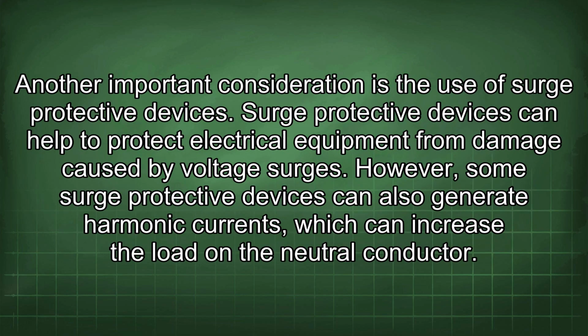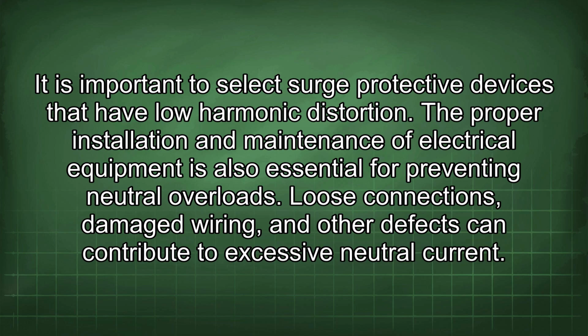Another important consideration is the use of surge protective devices. Surge protective devices can help to protect electrical equipment from damage caused by voltage surges. However, some surge protective devices can also generate harmonic currents, which can increase the load on the neutral conductor. It is important to select surge protective devices that have low harmonic distortion.